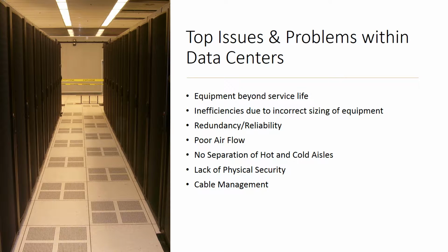There are a wide range of issues that can affect the data center. Some top data center issues include equipment that is beyond its service life, cabling and electrical circuits that are improperly labeled or not labeled at all, redundancy and reliability issues, or inefficiencies due to incorrect sizing of electrical and mechanical equipment. Poor airflow, no separation of hot and cold aisles, missing rack blanking panels, improper grounding, code violations, and even a lack of fire protection and physical security also cause problems.